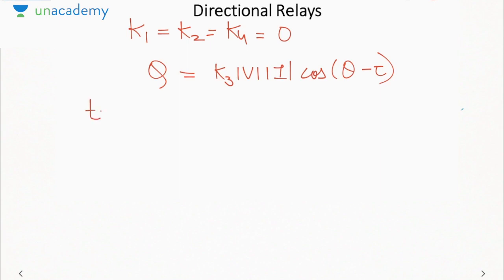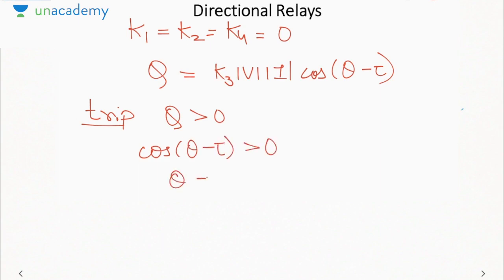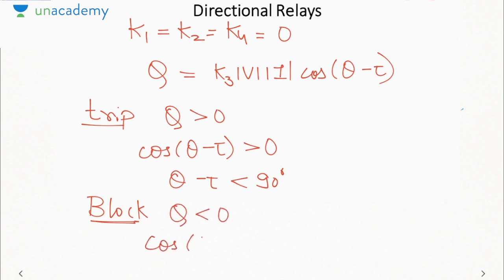Now for the relay to trip, the torque Q must be greater than 0. That means cos of (theta minus tau) must be greater than 0, or theta minus tau must be less than 90 degrees. For the relay to not operate, or we can call it block, Q must be less than 0. Cos of (theta minus tau) must be less than 0, or theta minus tau must be greater than 90 degrees.